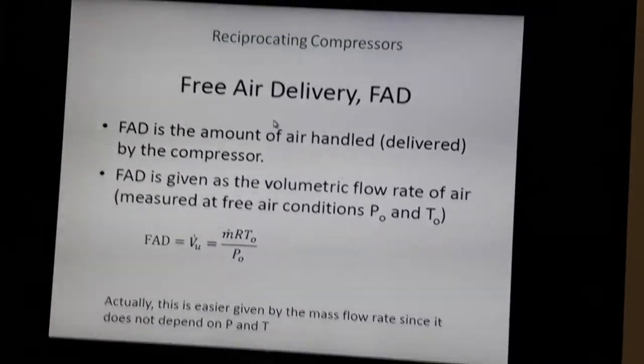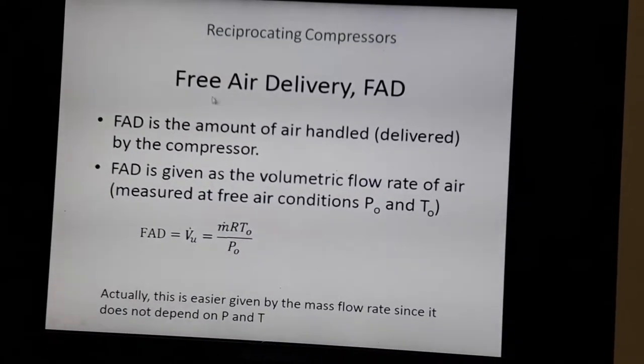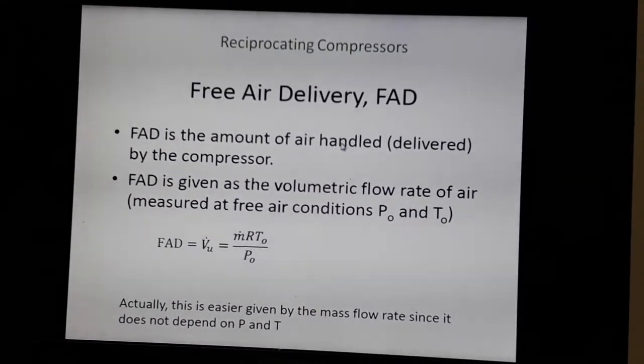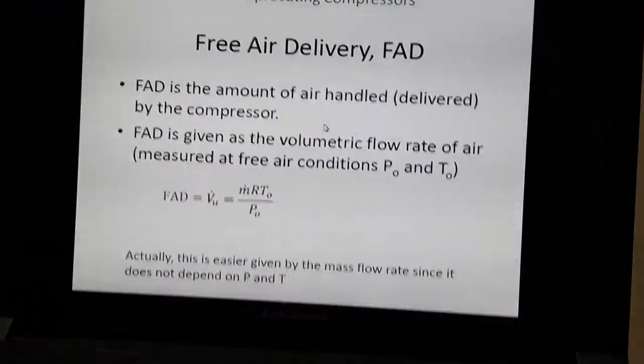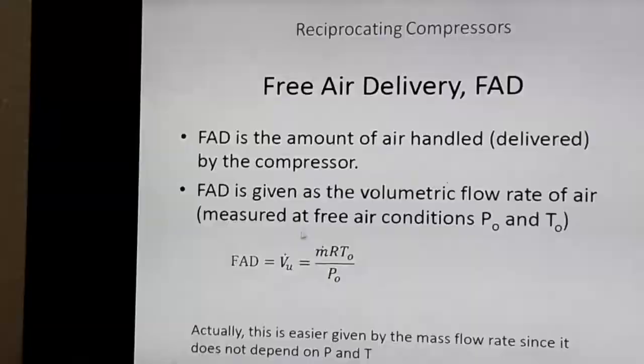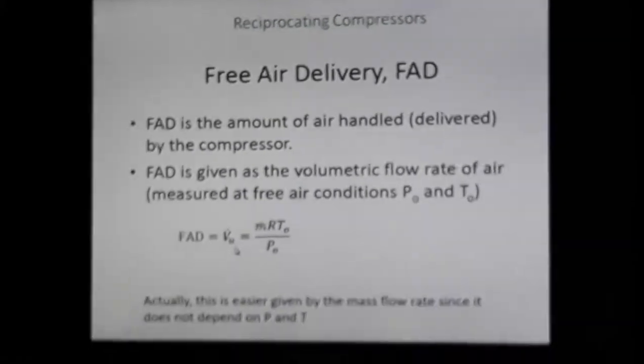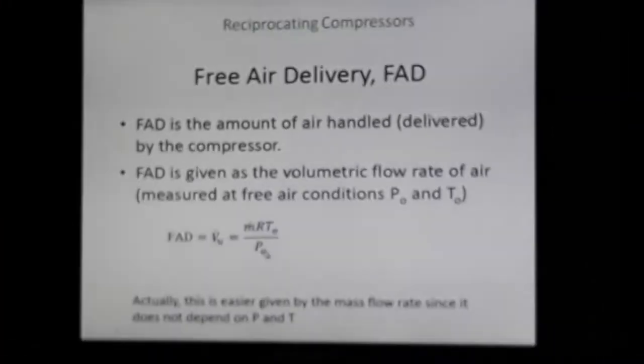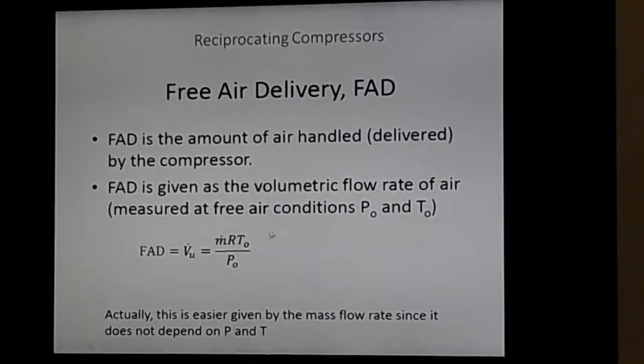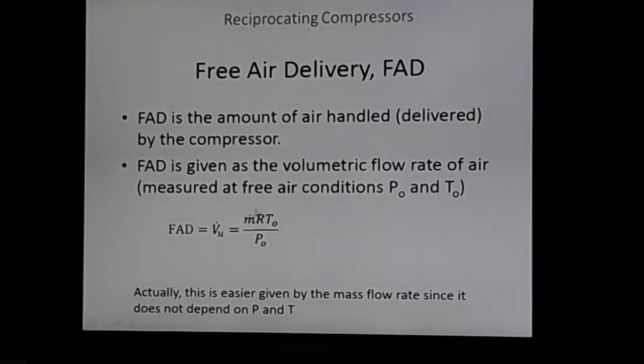Now let us discuss free air delivery, which is an important specification for a compressor. Free air delivery is the amount of air handled or compressed by the compressor, or equivalently the volumetric flow rate of air measured at free air conditions, that is at pressure p0 and temperature T0. From the general gas equation, free air delivery equals m-dot · R · T0 / p0, where T0 and p0 are the free air reference conditions.